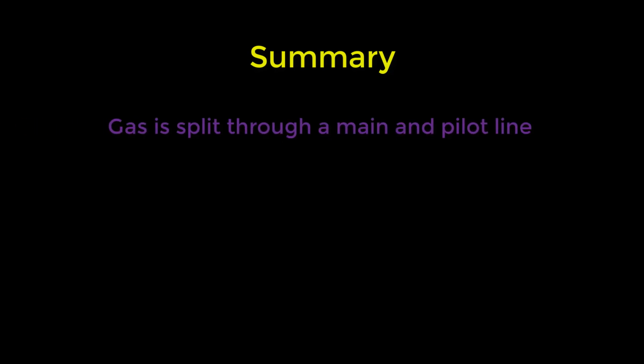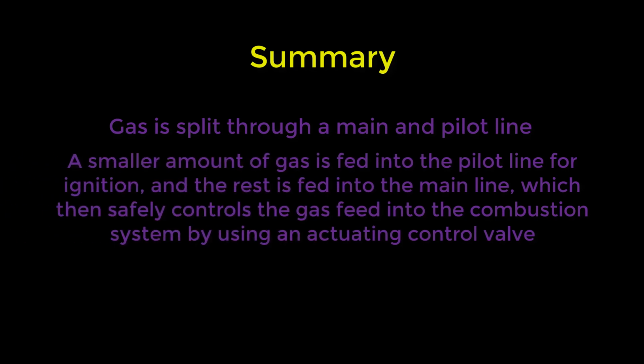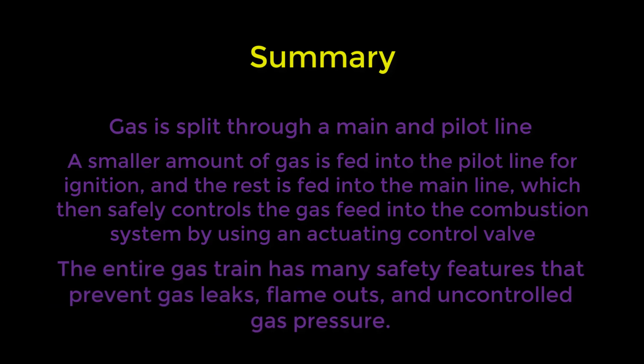In summary, the gas is split through a main line and a pilot line. A smaller amount of gas is fed into the pilot line for ignition, and the rest is fed into the main line, which then safely controls the gas feed into the combustion system by using an actuating control valve. The entire gas train has many safety features that prevent gas leaks, flameouts, and uncontrolled gas pressure.